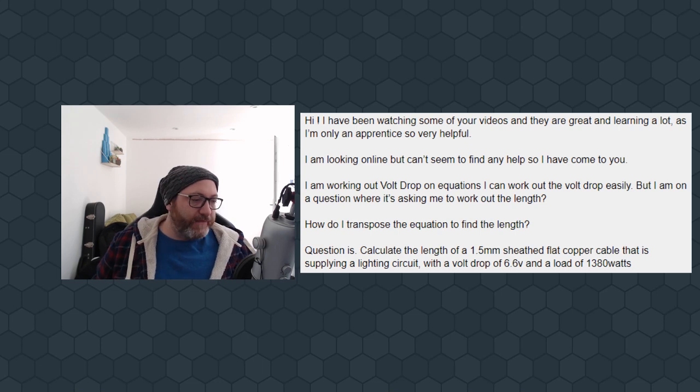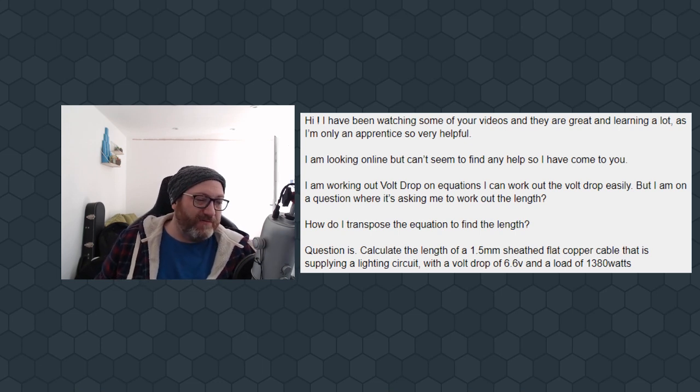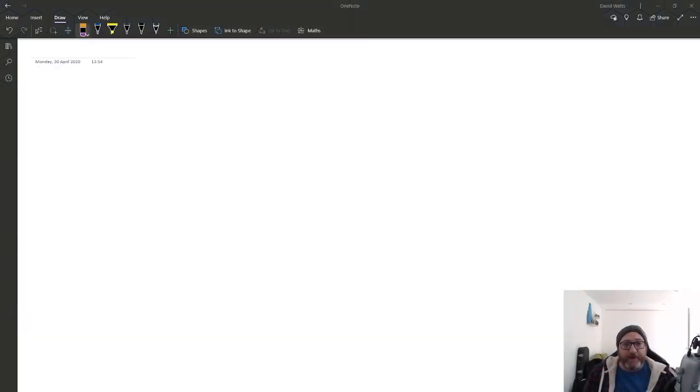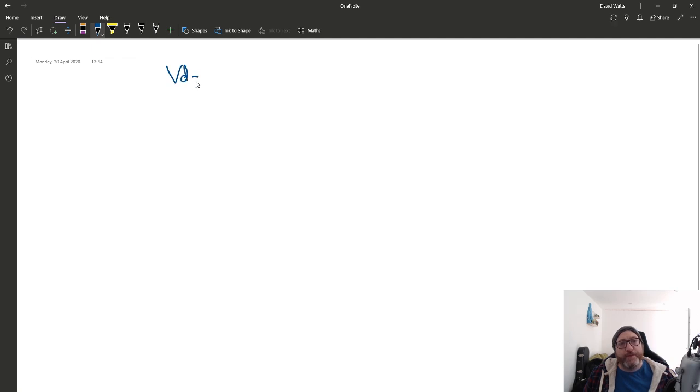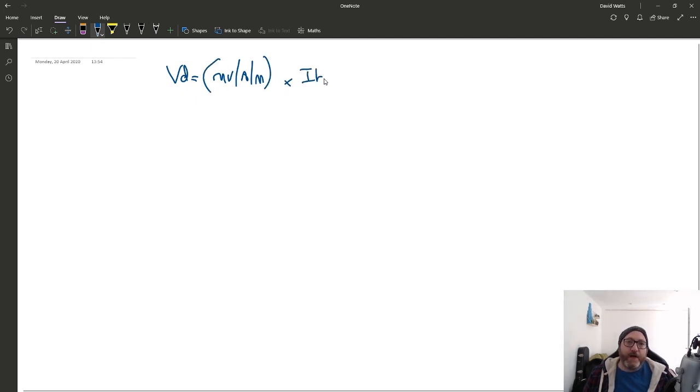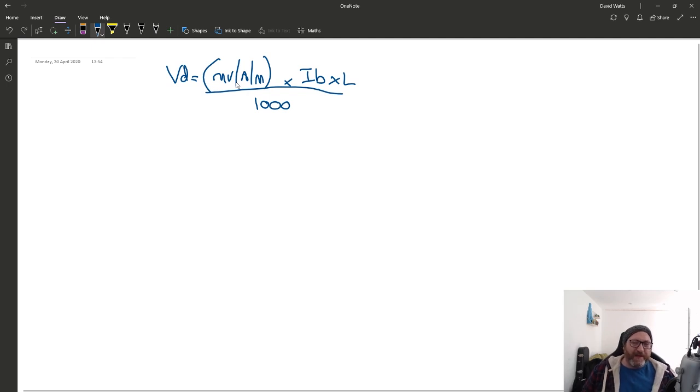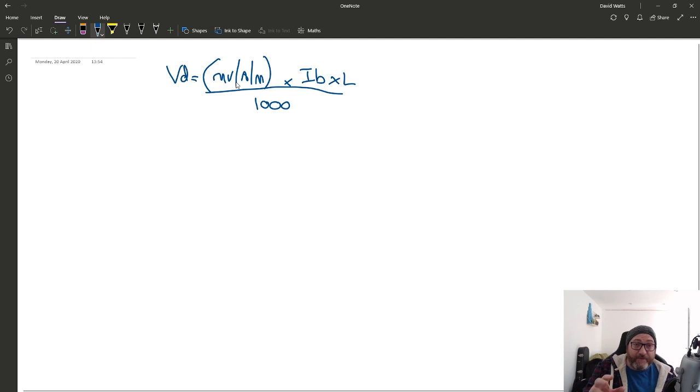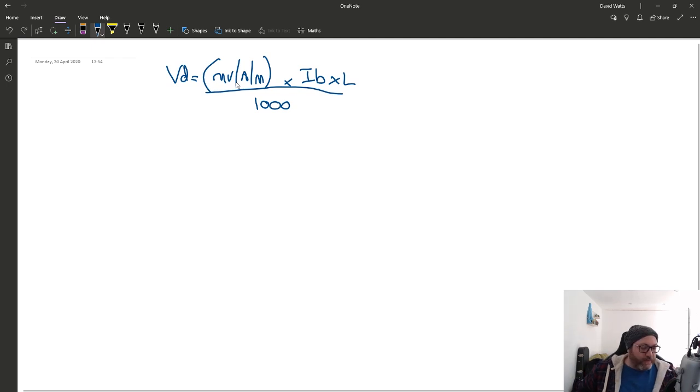A couple of key things that we can take from this. The first, I'm just going to try to write this as I go. The first is knowing what the Volt Drop formula is initially, just in case you're not too familiar with that. So, the Volt Drop is equal to the millivolt per amp per meter value, multiplied by the design current, multiplied by the length over a thousand, which gets us from the millivolts to volts. That shouldn't be too much of a problem. If you're not sure of that, then you need to go there first, because that is what they're messing around and playing about here.